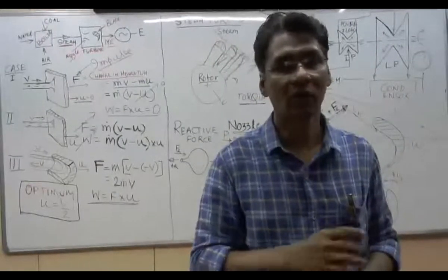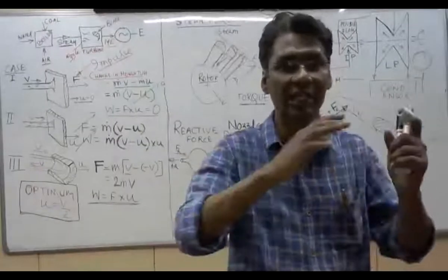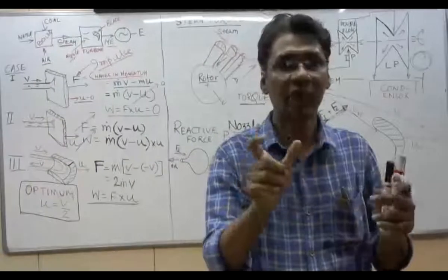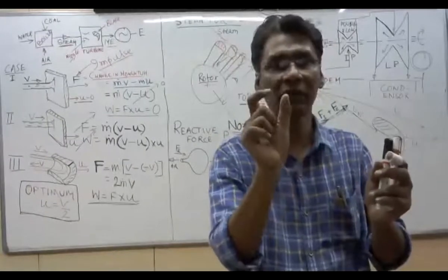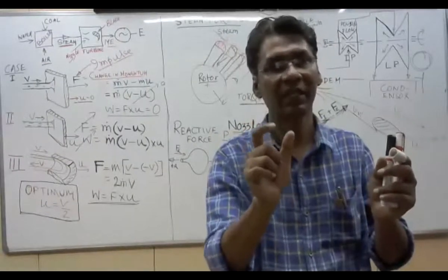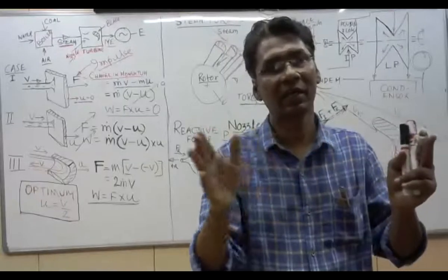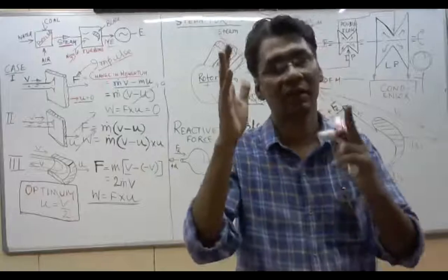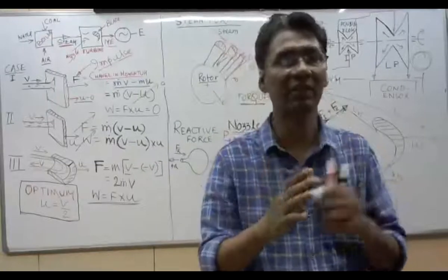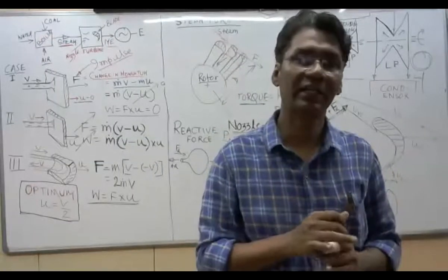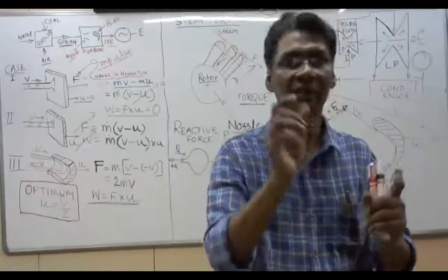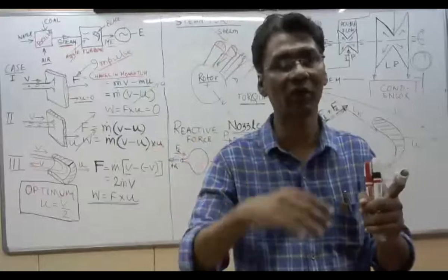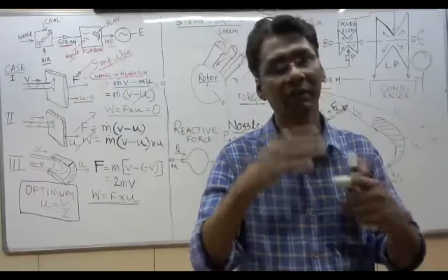There is no expansion of the turbine as such, there is expansion of steam. The turbine expands thermally only by a very little amount, and that is called turbine expansion. Rotor expansion minus casing expansion is called differential expansion. That is not controlled, it is allowed, and how much expansion is allowed is maintained. Beyond this limit, the turbine will trip and be stopped.